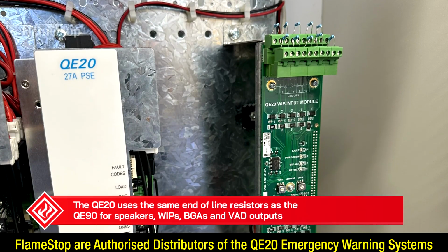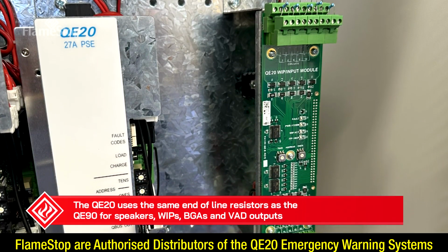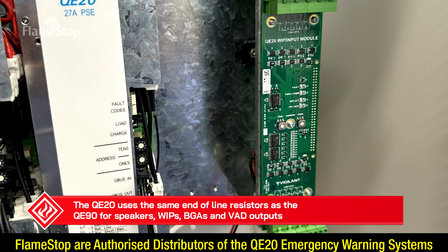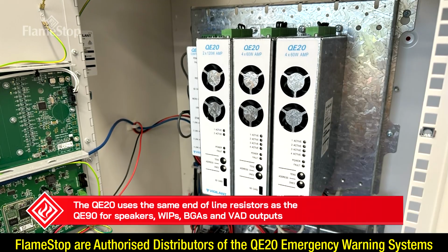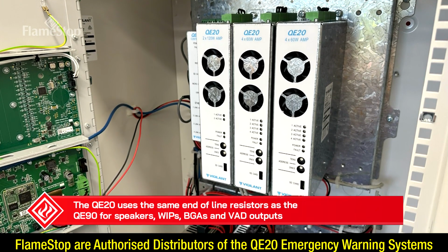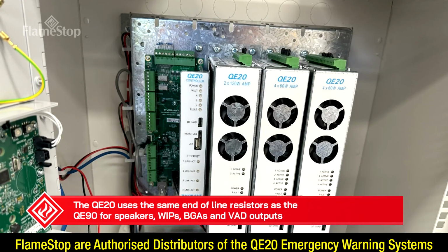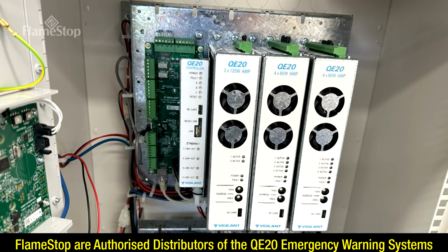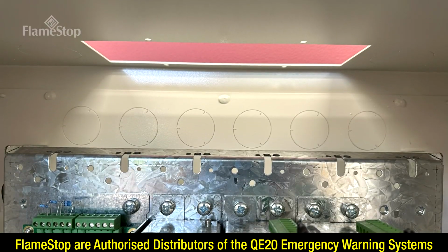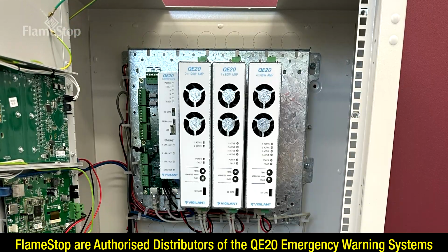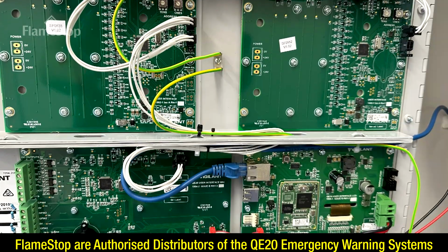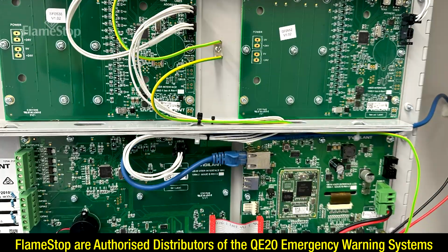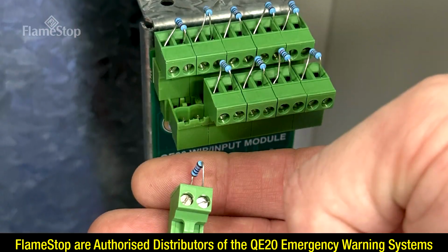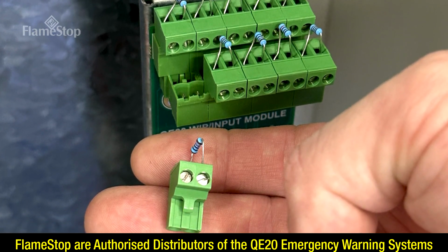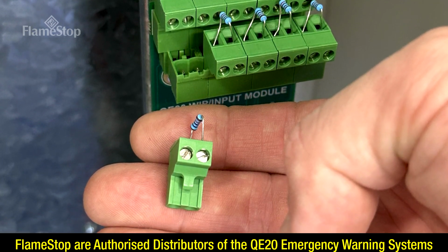The QE20 uses the same end-of-line resistor values as the previous QE90 model for its WIPs, BGAs and visual alarm device outputs. This is just another great feature of the QE20 system, making it perfect for retrofit installations. The installers love the mechanics of the QE20. The modular construction allows cards to be placed in any position on the module mounting frame for easier site expansion or upgrades. The field wiring connects to modules via removable connectors for easy termination and module testing or swap out.